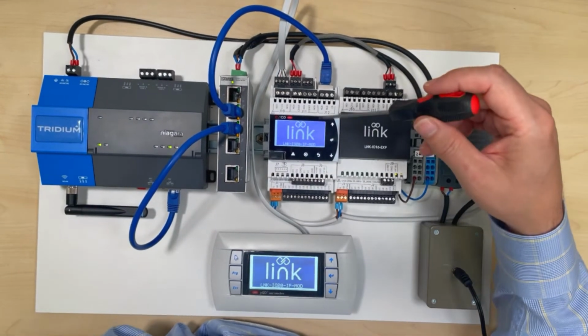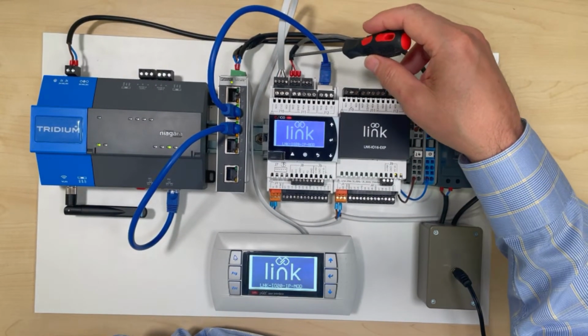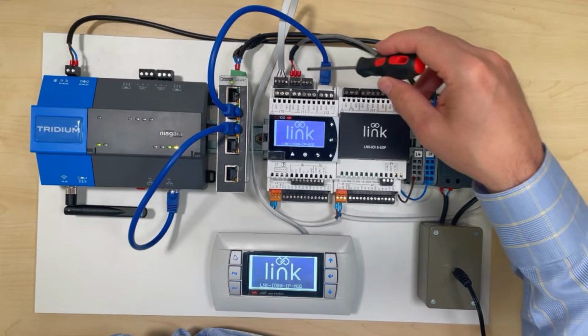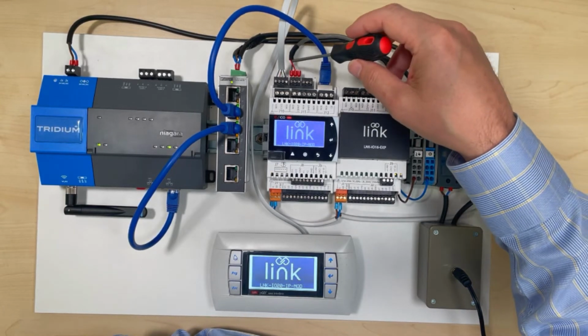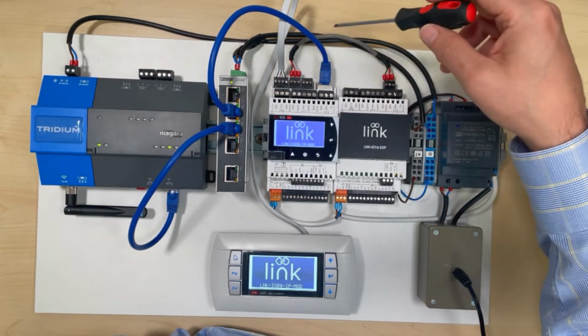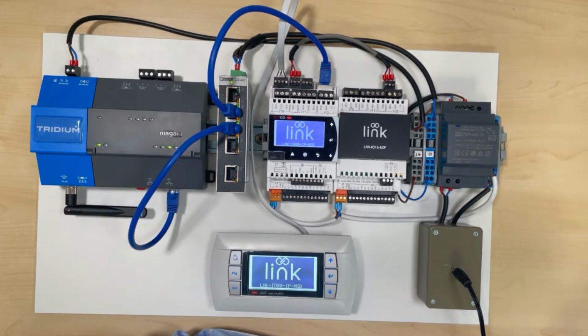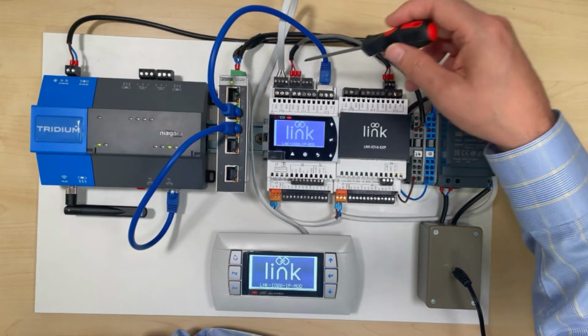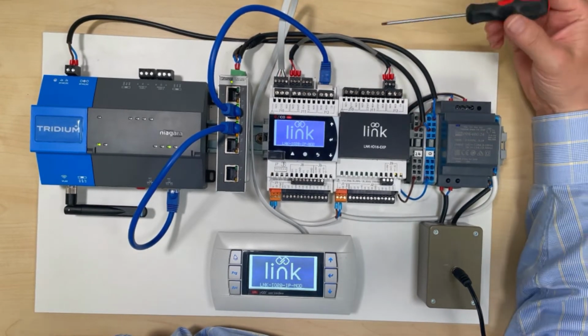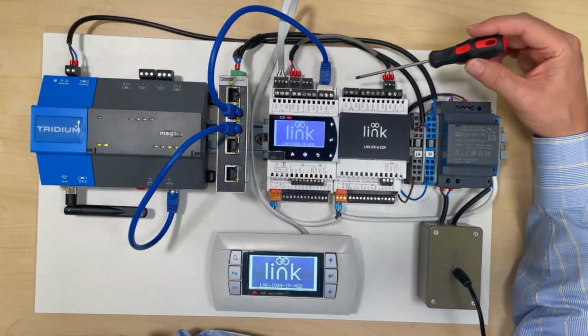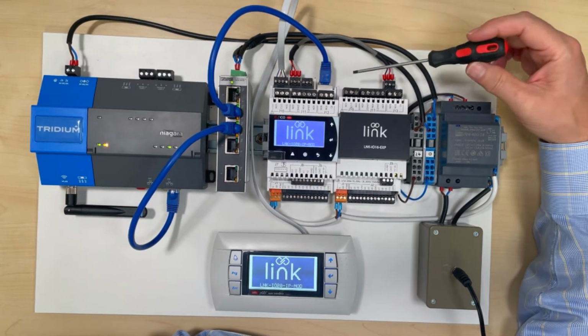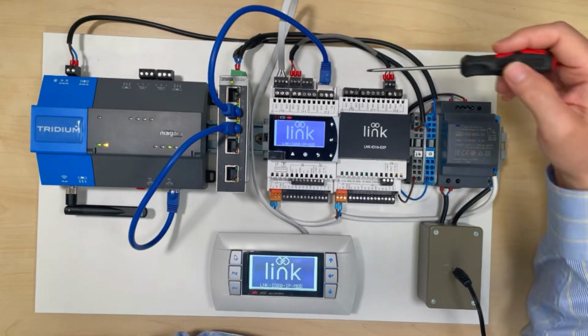So the Link IO20 is then linked on a field bus network. This is different from the Modbus and maybe MSTP, BACnet MSTP. Then it talks to the expansion modules. Remember we said we can have up to 10 of them. I'm only using one here through this bus here. There's a set of dip switches on the Link IO down here. This sets the address of each one and the baud rate, which our manual tells you how to set.